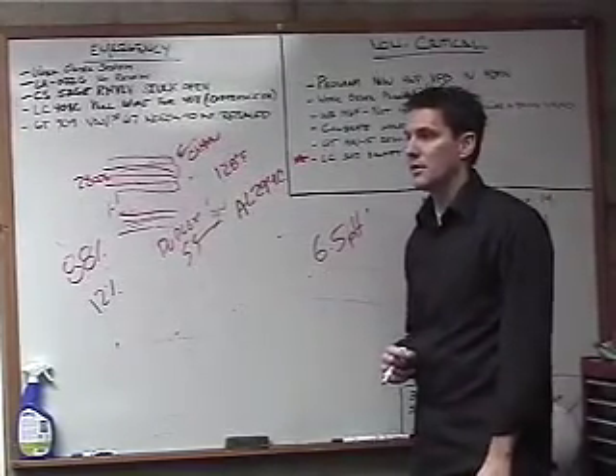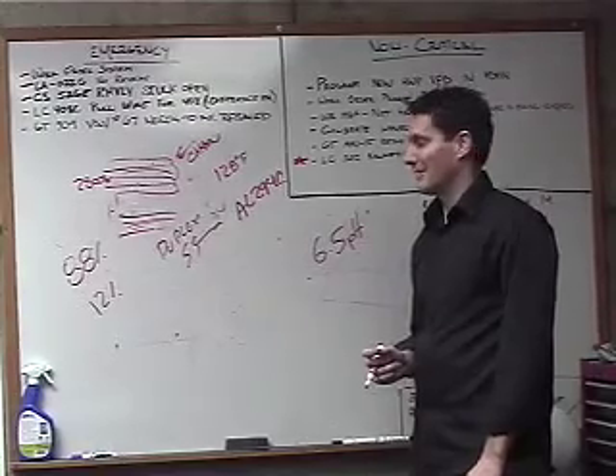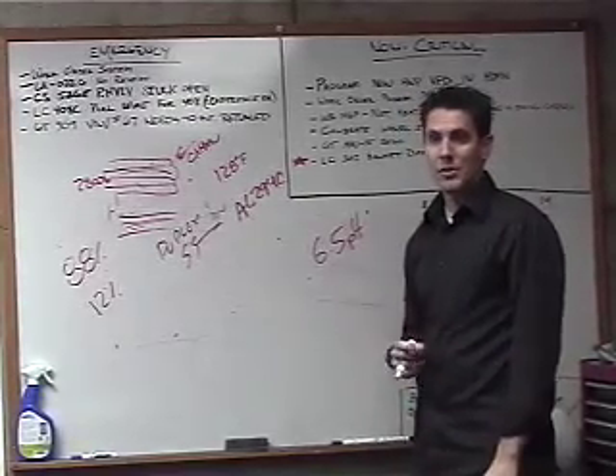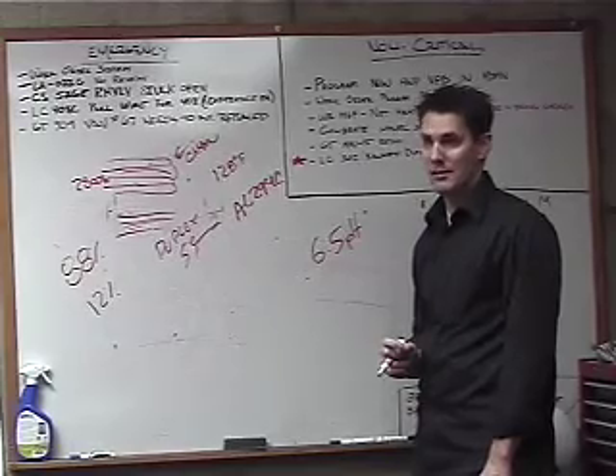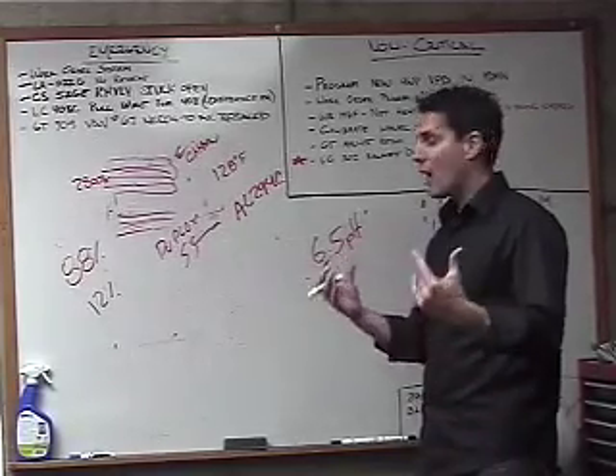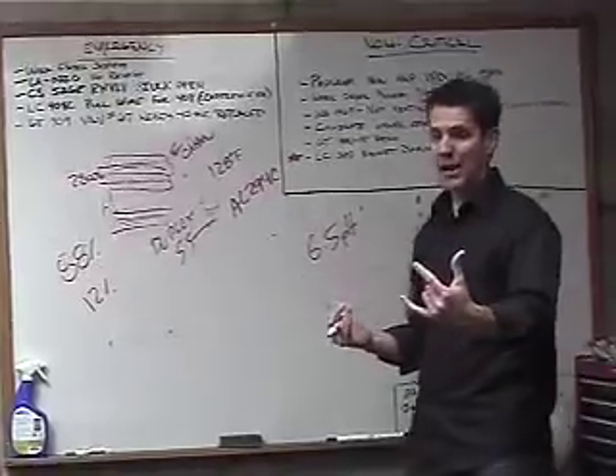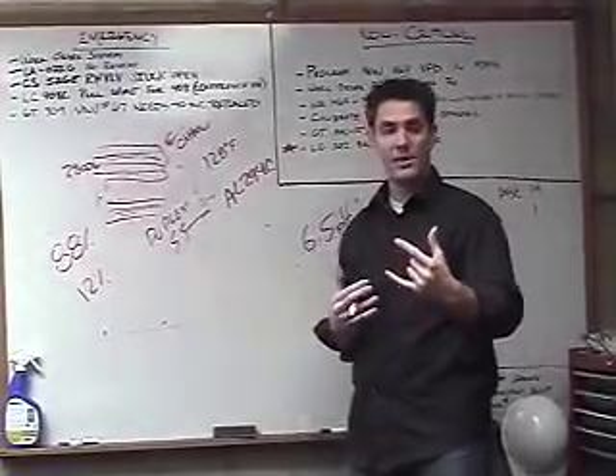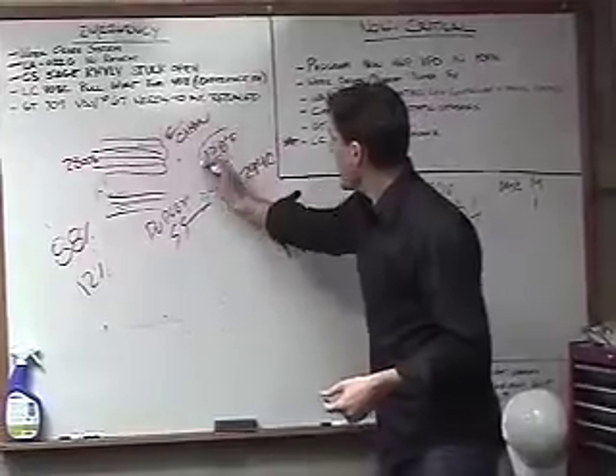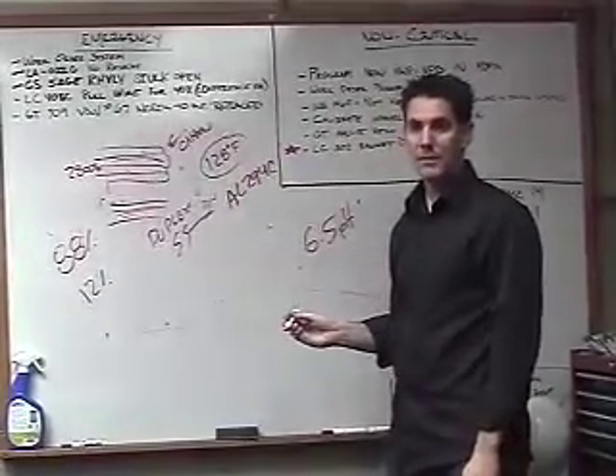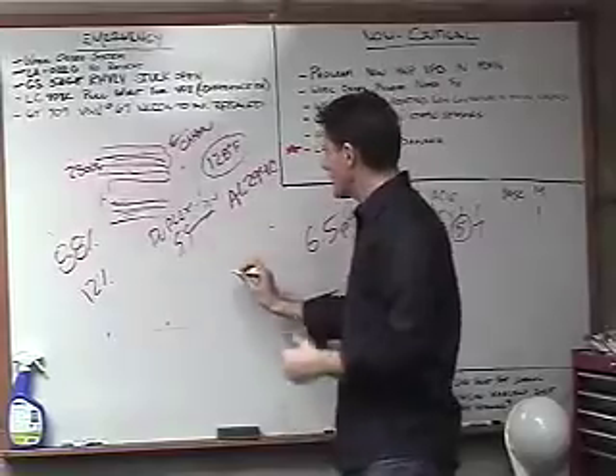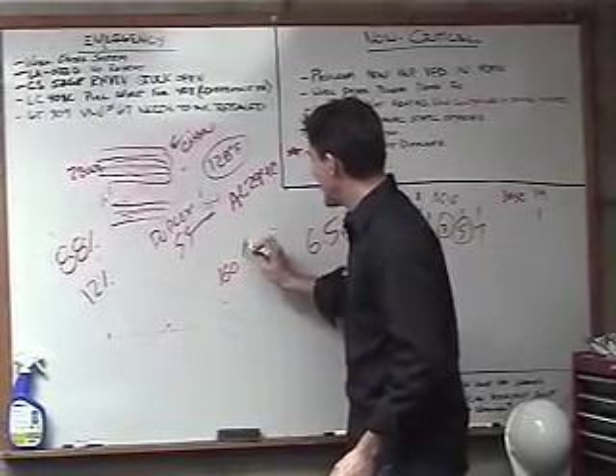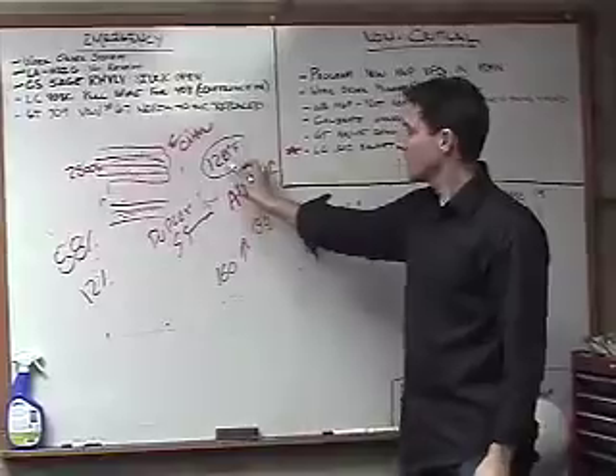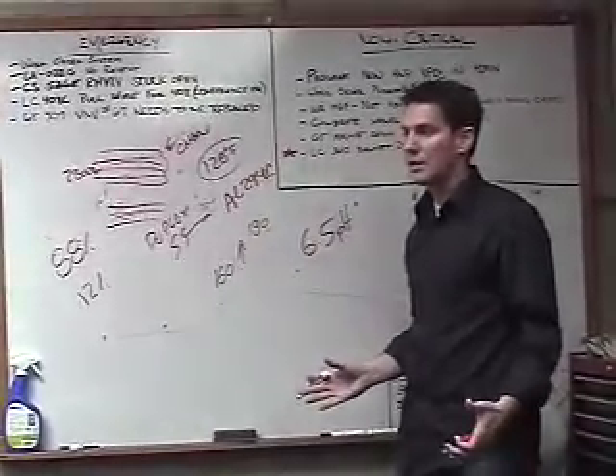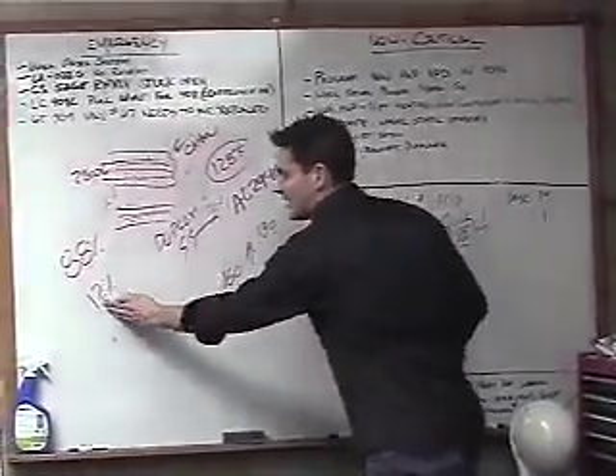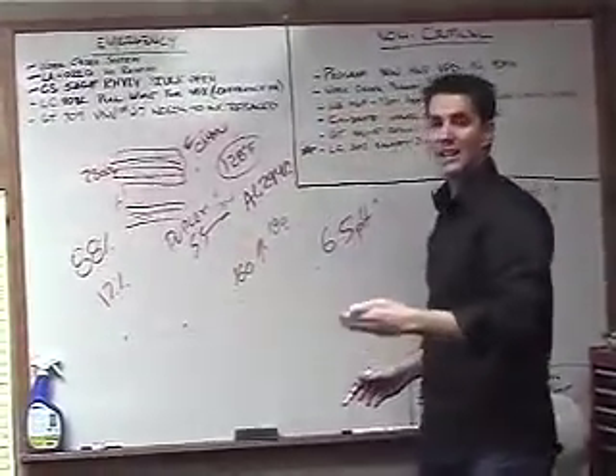So what's going to happen? Keeps the pipes clean. What are your drain lines constructed out of? Cast iron. And over time, depending on how often you condense, if your water's coming back at 160 and you're heating it up to 180, will you ever condense? Again, my flue gas has to get to 128 degrees Fahrenheit. So if my water coming back to my boiler is 160 and I heat it up to 180, will I ever get my flue gases this cold? You can't. That's why my boiler really can't get into this efficiency until my water temperatures get less than what?